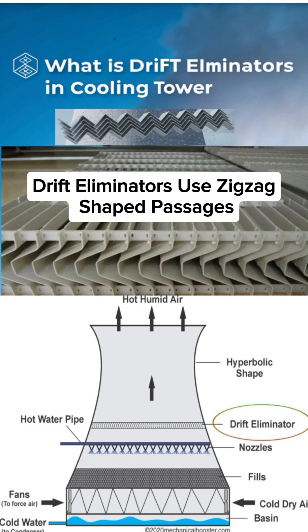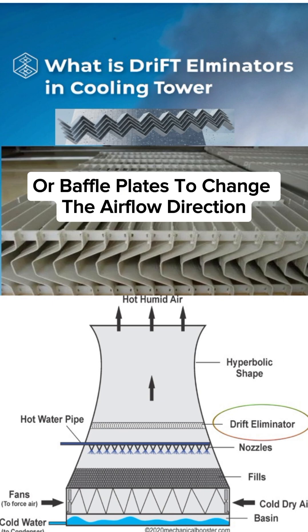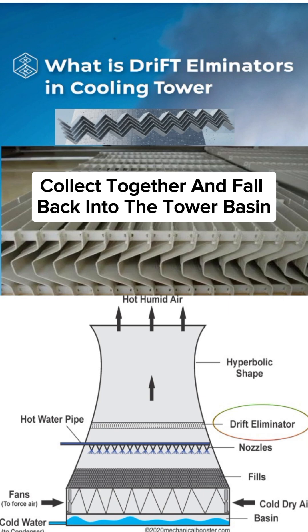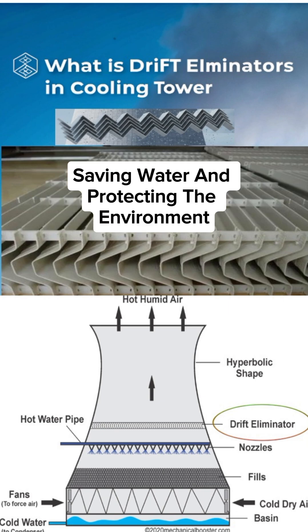Drift eliminators use zigzag-shaped passages or baffle plates to change the airflow direction. When moist air passes through, water droplets hit the surfaces, collect together, and fall back into the tower basin, saving water and protecting the environment.